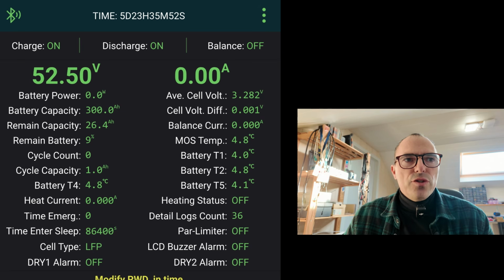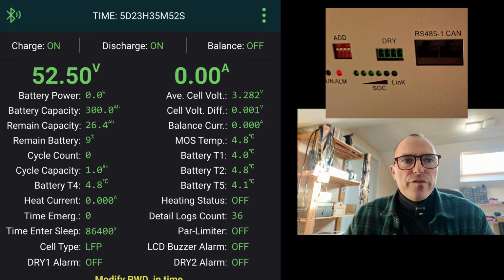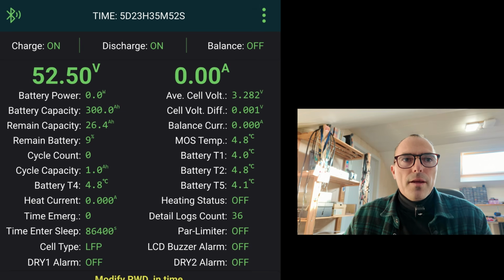It's a bit the same for the dry 1 and dry 2 alarm. There is a small relay inside the BMS and you can set this for the same parameters. There are, I think, a dozen of parameters like state of charge, low voltage, high voltage, temperature, where you can trigger a relay. You can access these dry contacts on the front of the panel. It's the green breakout board you see, and there you can make a contact with a wire and activate a light or an external alarm. But more on that later in the YouTube clip.